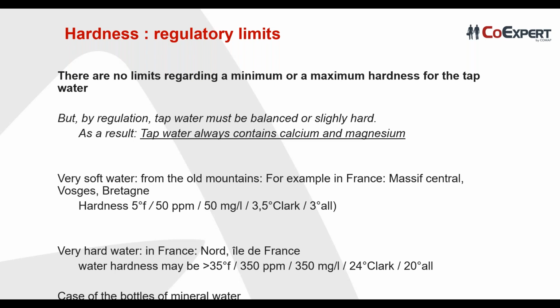In the regulation, yes, there is no limit regarding calcium and magnesium, so regarding the hardness. But in the regulation, it's mentioned that tap water must be balanced or slightly hard. That means if you want the water to be balanced or slightly hard, it's necessary to have calcium and magnesium inside. So even if there are no limits regarding the hardness, it's impossible to have water free of calcium and magnesium because the water must be balanced. So pay attention to that.